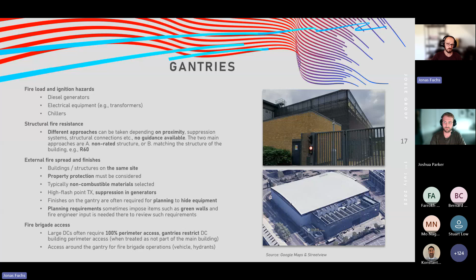With regards to the fire brigade access that Josh already mentioned on the previous slide, large DCs would typically require 100% perimeter access, and gantries restrict that access, so the perimeter access strategy becomes effectively non-compliant with the approved guidance or with BS 9999. So access around the gantry and to the gantry needs to be considered, as well as egress from the gantry itself.